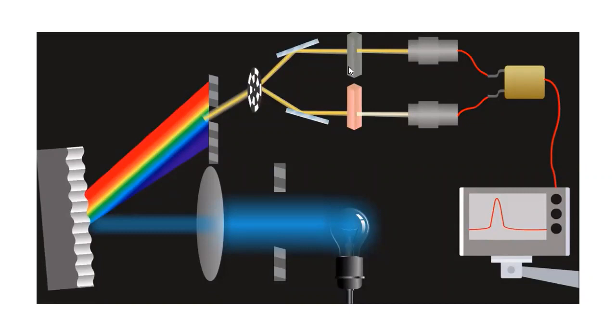Then you have two types of cuvettes — one is the reference and one is the sample. The cuvette is a material made from quartz. We use quartz material because quartz does not absorb UV or visible radiation — it will transmit both. Glass material would transmit visible rays but will absorb UV radiation. That's why we don't use glass material here; we use quartz cuvettes to hold both the reference and sample solutions.